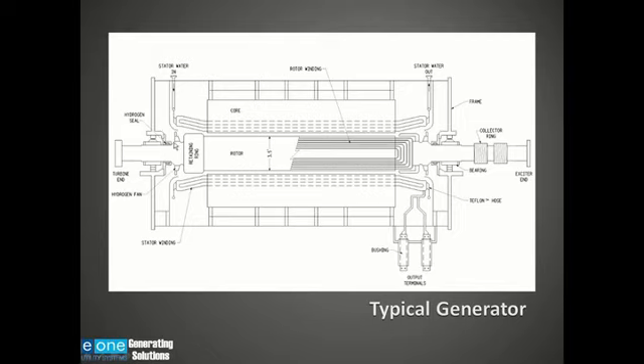I'm pointing these out to you here. There's this hydrogen seal on the turbine end of the generator. There's a hydrogen seal on the exciter end of the generator. You will also note that this particular generator has two fans. There's a fan on this end and a fan on this end, which is used to circulate the hydrogen. These fans will create a high pressure and low pressure in the generator, which we'll discuss later. Some generators don't have fans, but have what are called blowers that will be used to circulate the hydrogen, and they are mounted on the rotor also.